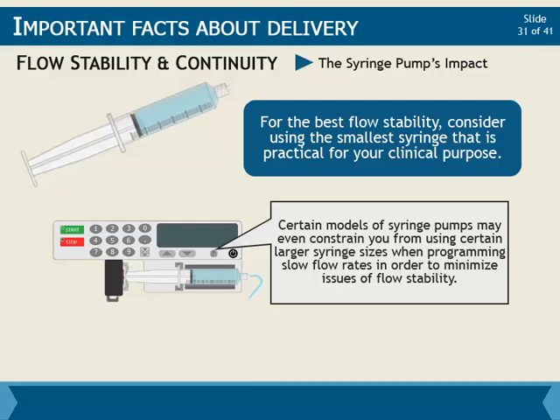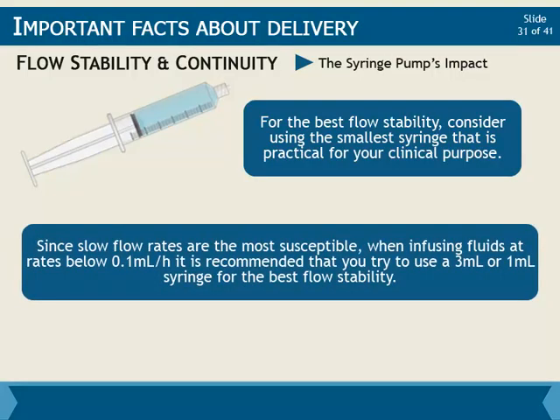Certain models of syringe pumps may even constrain you from using certain larger syringe sizes when programming slow flow rates in order to minimize issues of flow stability. Since slow flow rates are the most susceptible when infusing fluids at rates below 0.1 milliliter per hour, it is recommended that you try to use a 3 milliliter or 1 milliliter syringe for the best flow stability. However, 1 milliliter syringes do have a limitation when used with some syringe pumps with regards to occlusion detection. We will discuss this limitation in the next module.